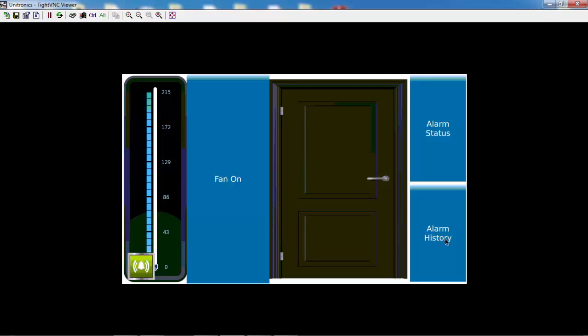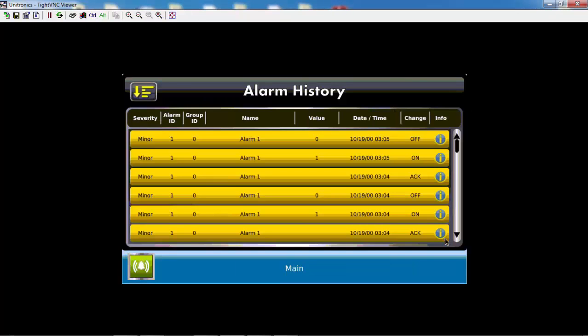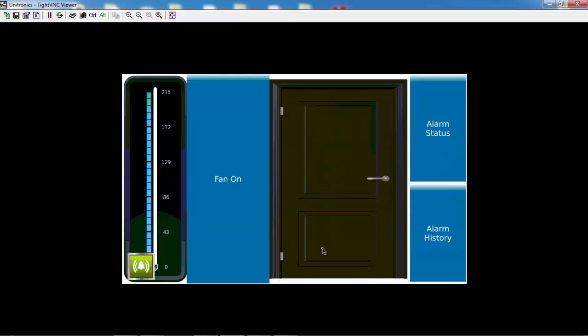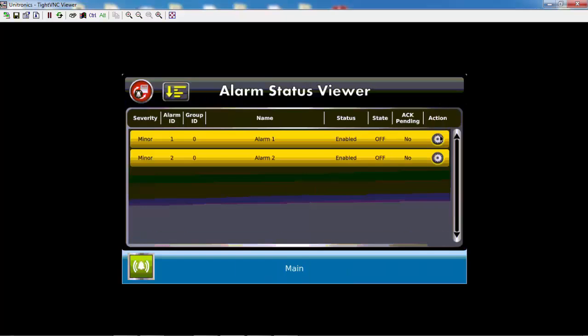Here, you can view and sort the alarms, but not edit them. You can also use the alarm status widget for easy alarm management. From here, you can view alarm statuses, enter comments, and suspend alarm actions via disable and shelve. Disable will completely disable a single alarm. Shelve will temporarily disable a single alarm based on a defined shelf time in the alarm status viewer.